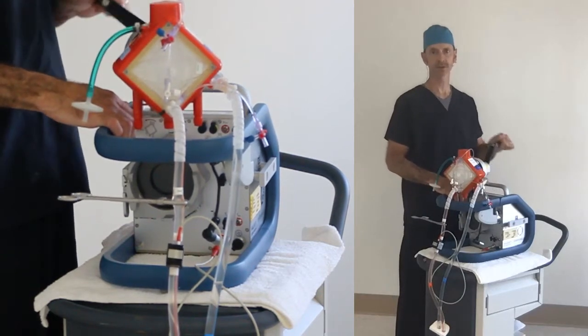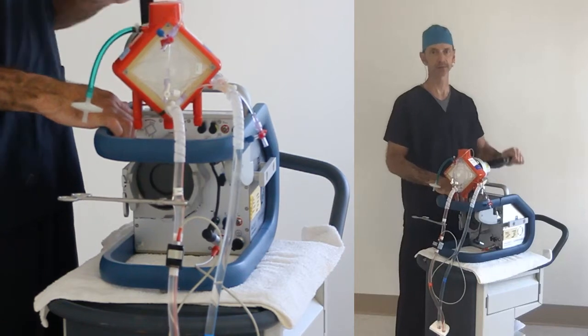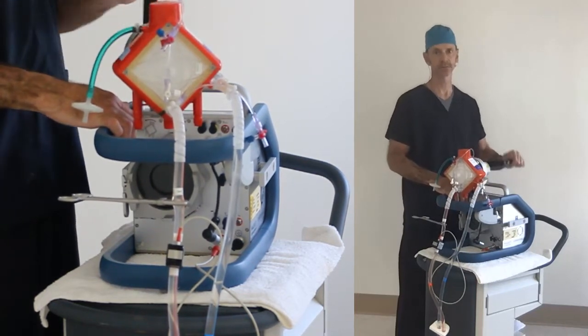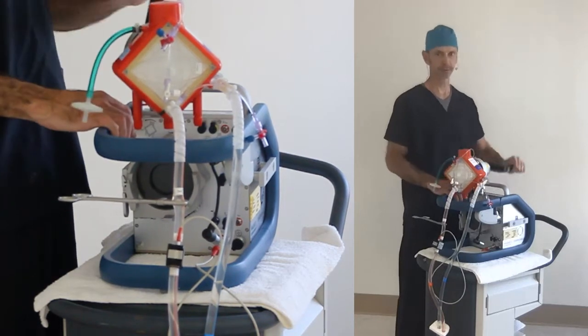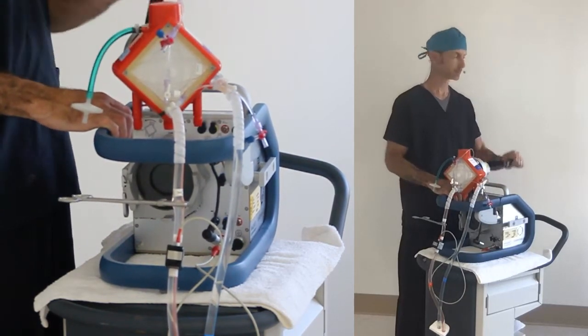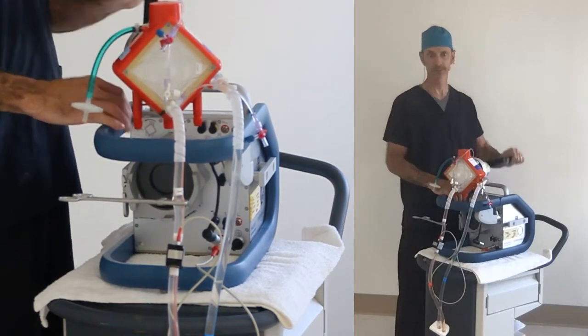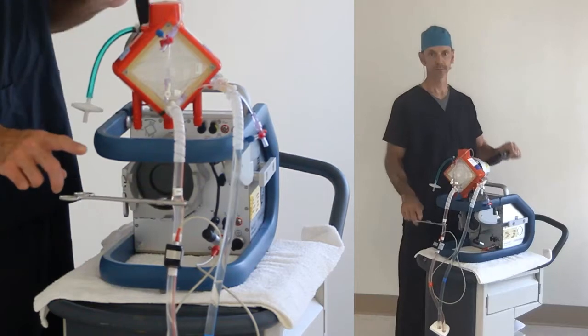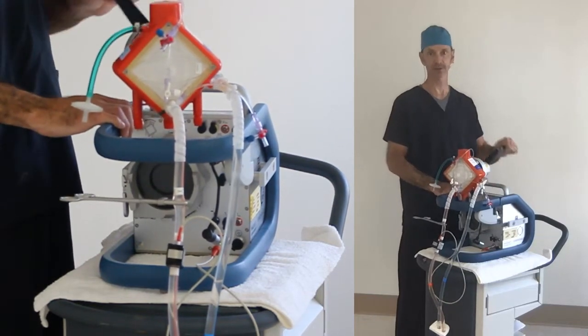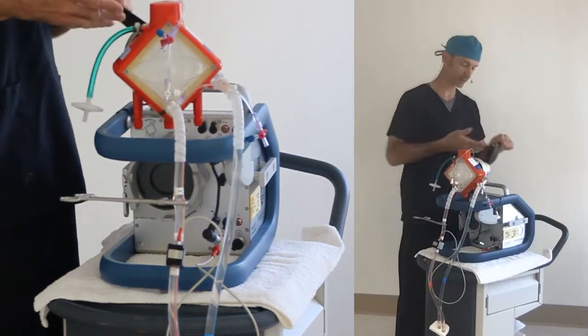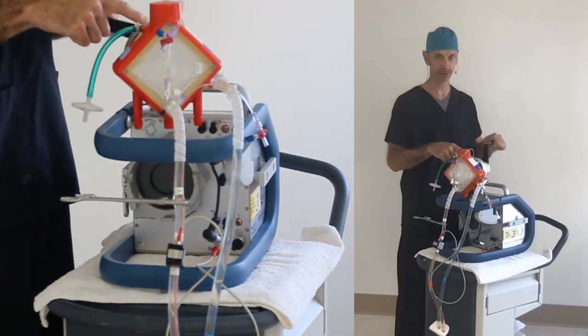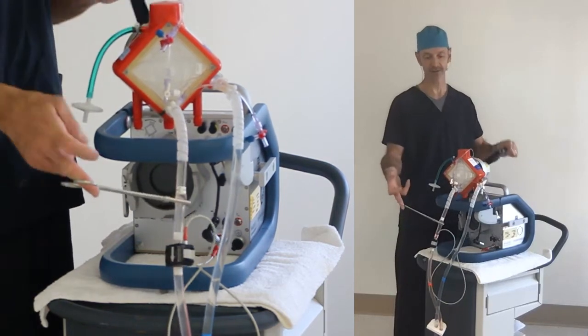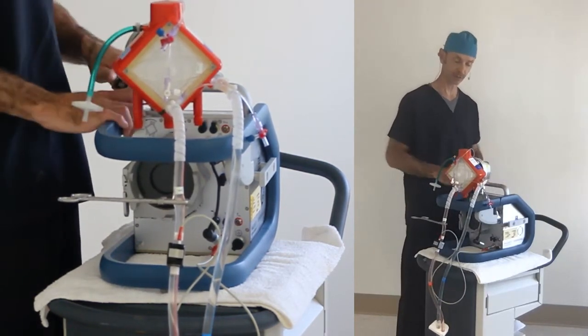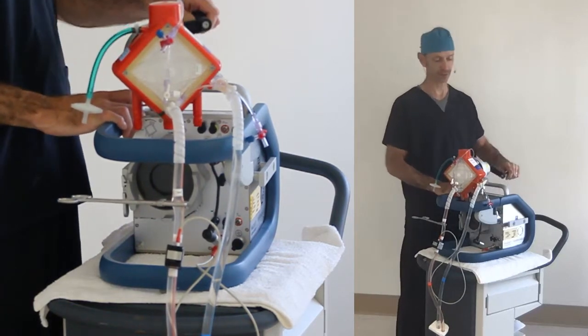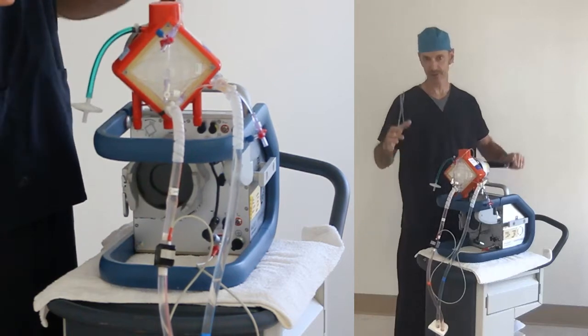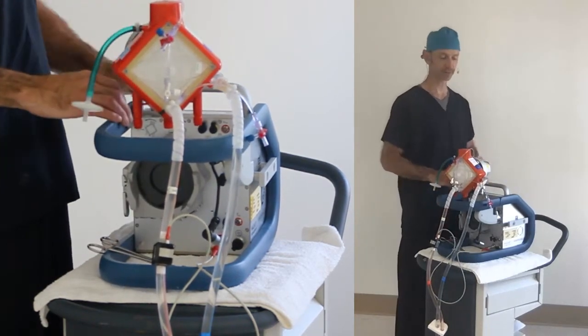Number one, most common mistake is happening right now. I've got 3,000 RPMs. Good things must be happening. Frequently forgotten, probably like 50% of the time in training exercises. Forget to take that off. All your data, which is, there's only one piece of data now, RPMs, your data says they're good, but there really isn't any flow until we take that off. So actually they should, when they flip the handle down, start cranking to about 1,000, then they should take the clamp off, and then come up to full flow.